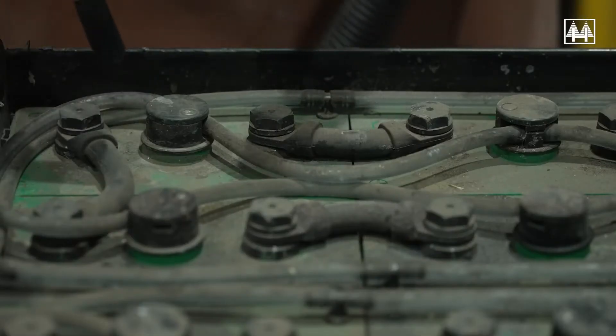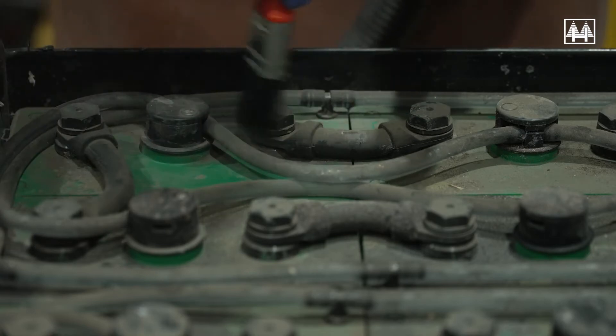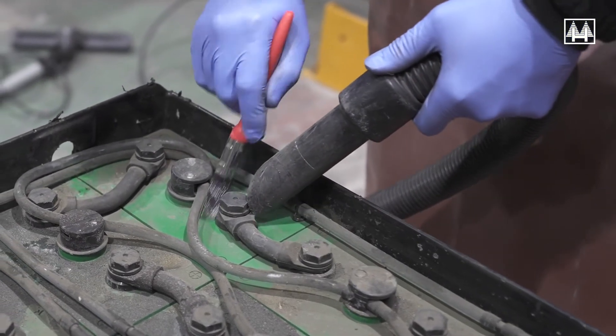If your battery has dry dust on the cell lids, it should be cleaned away using a paintbrush and a handheld battery-powered vacuum cleaner. If this is done regularly, it will remove the risk of your battery getting damp from electrolyte gassing.